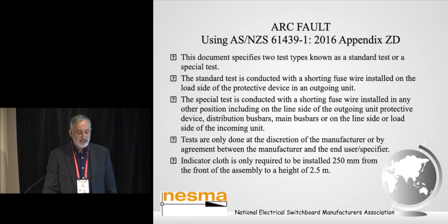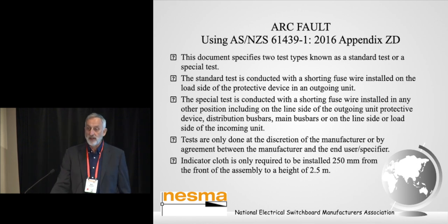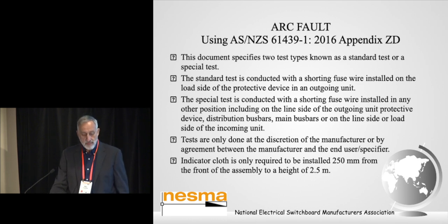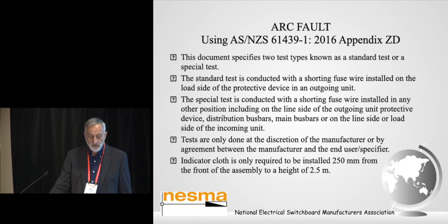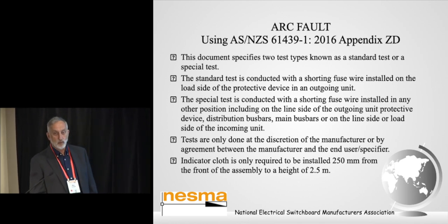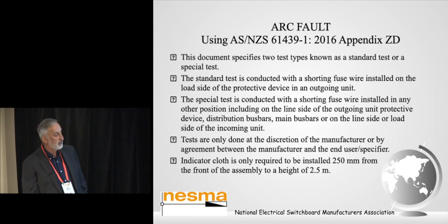Tests are only done really at the discretion of the manufacturer or by agreement between the manufacturer and the end user or specifier. And the indicator cloth used for an Appendix ZD test is installed 250 mil from the front of the assembly to a height of 2.5 metres. And it's a thin white cotton, a double layer of cotton gauze.